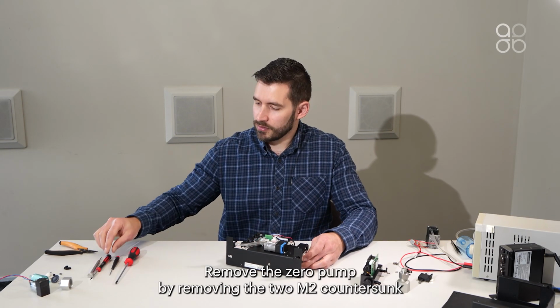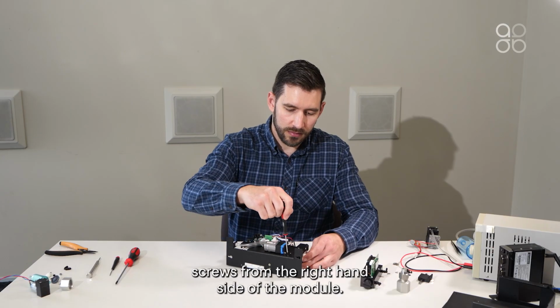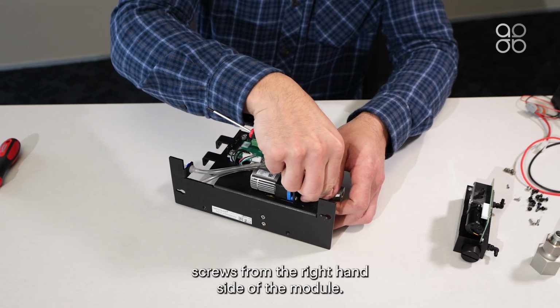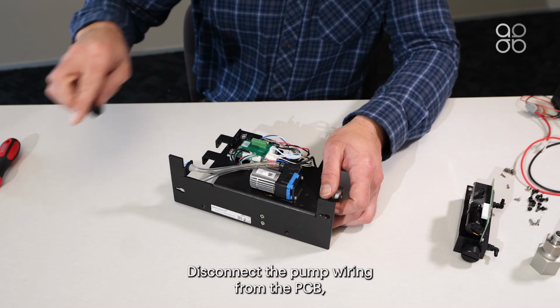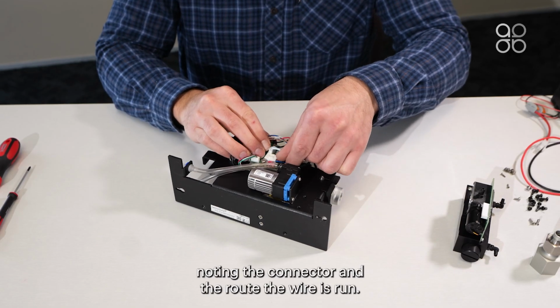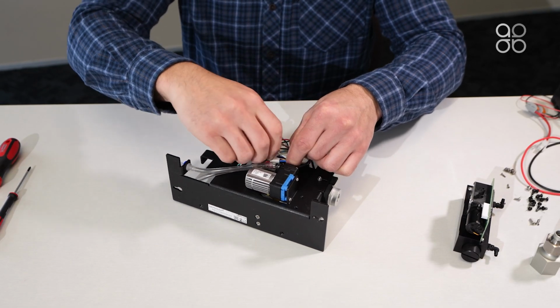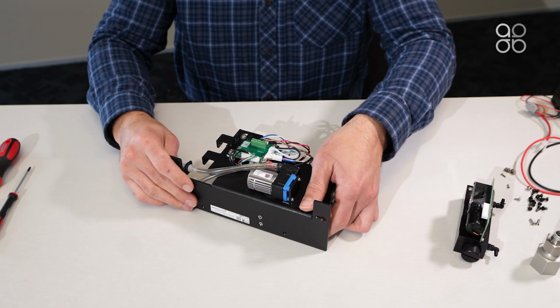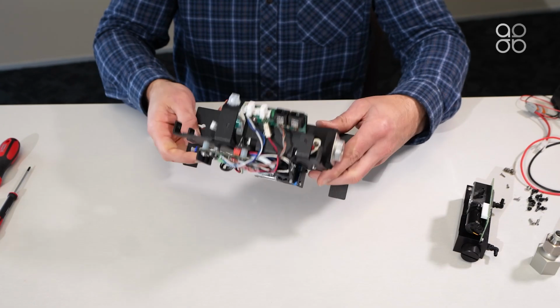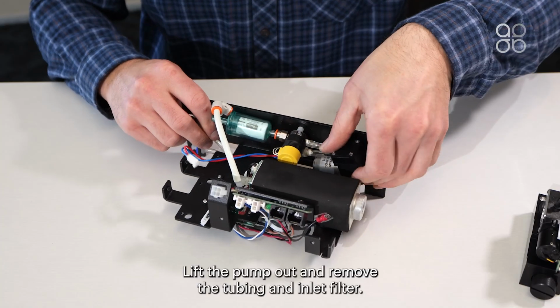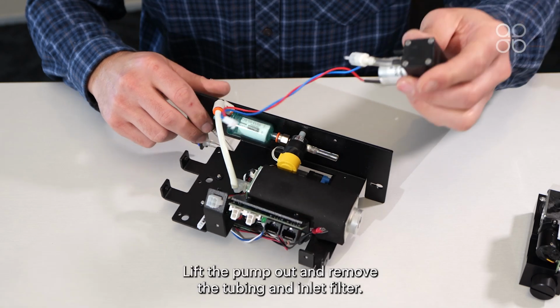Remove the zero pump by removing the 2 M2 countersunk screws from the right-hand side of the module. Disconnect the pump wiring from the PCB, noting the connector and the route the wires run. Lift the pump out and remove the tubing and inlet filter.